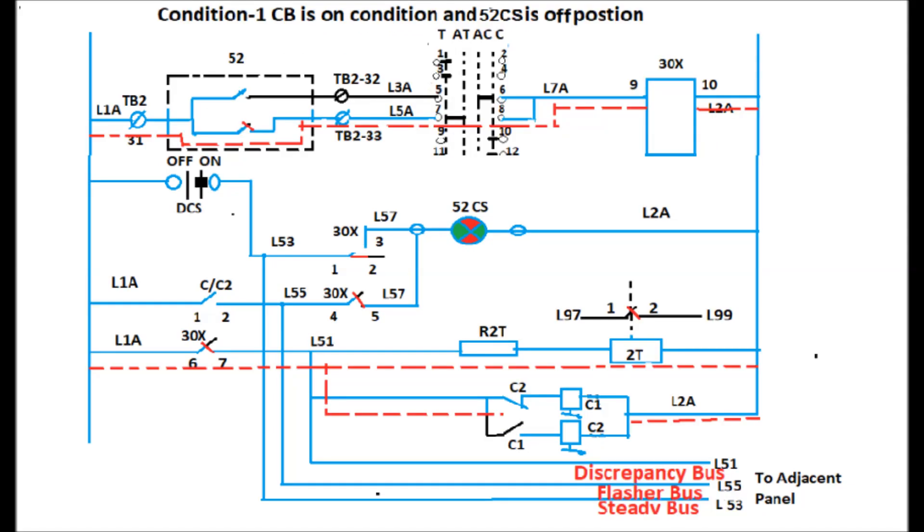Similarly, after the closing of CB, if we move the switch position to its latch off position without pressing the switch, the discrepancy will occur between the state of CB and switch position of CB. Thereby it will lead to energize the discrepancy and flasher bus and lead to flashing of the lamp in the control switch as shown in this figure.